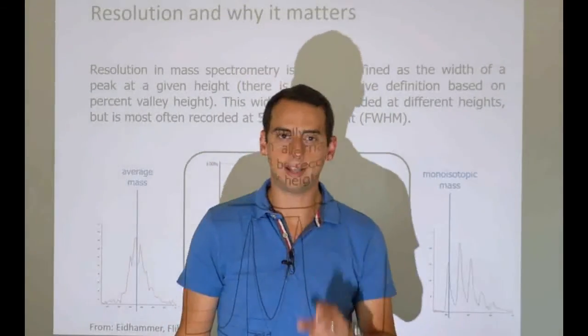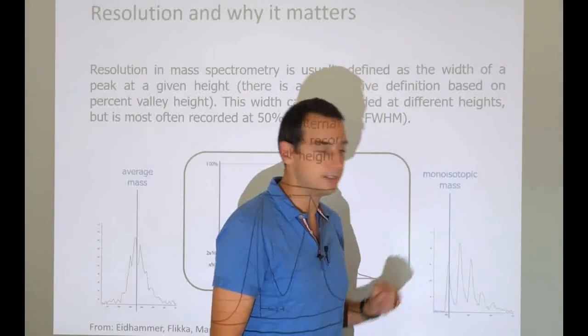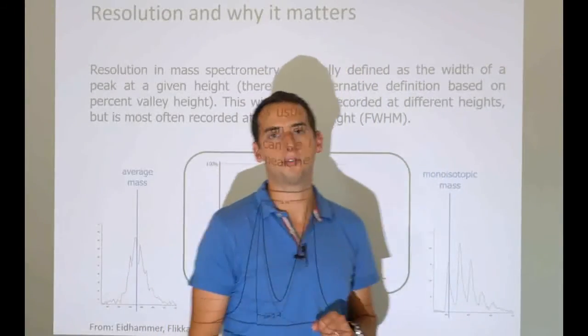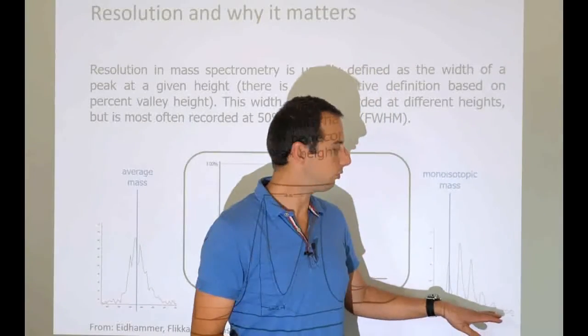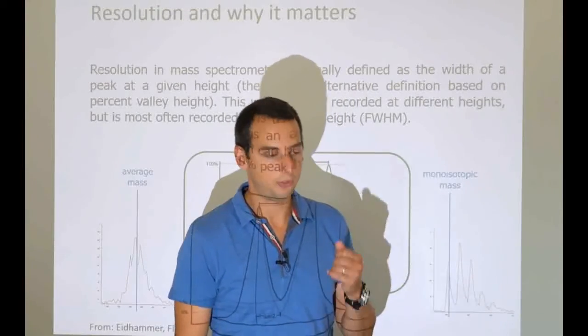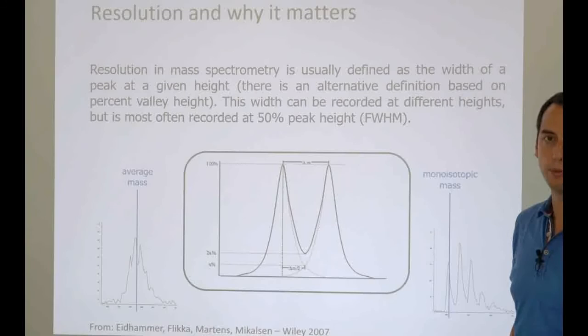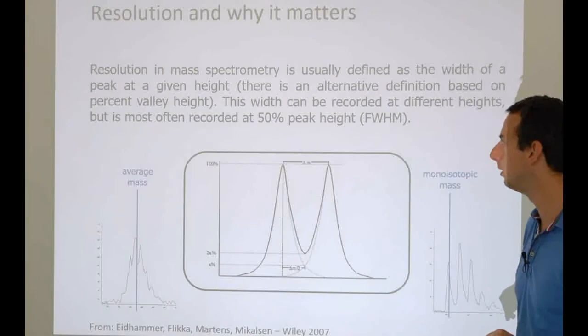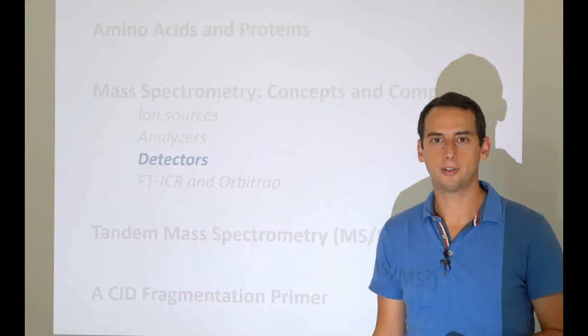We can actually calibrate this because we have multiple such measurements — at least two consecutive isotope spacings. That is how we can get the charge state of the analyte from a high-resolution instrument. Most modern instruments will have isotopic resolution. The big exception remains the ion trap, which will not be able to offer it. Time-of-flight instruments can do it, and we will see later that Orbitrap and Fourier transform instruments will also be able to do it. So that is why resolution matters — not just because it gives you more accurate mass readings, but also because it allows you to determine the charge state, and for electrospray we really need that piece of information. With that, we're done talking about analyzers, and our next lecture will be about the detectors. Thank you very much, and see you soon.